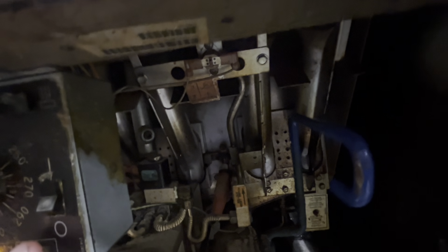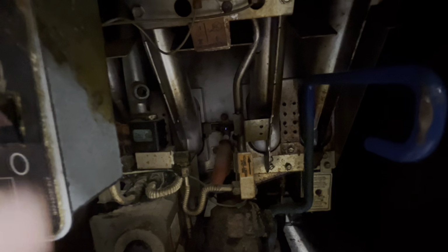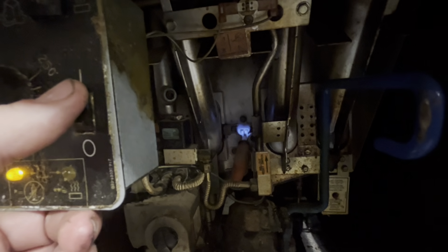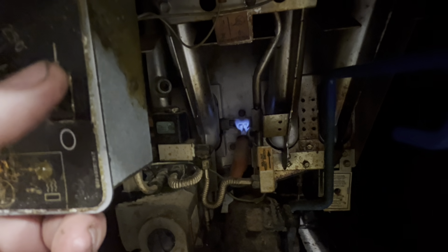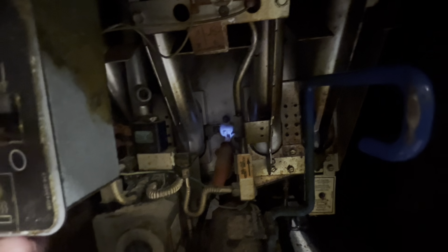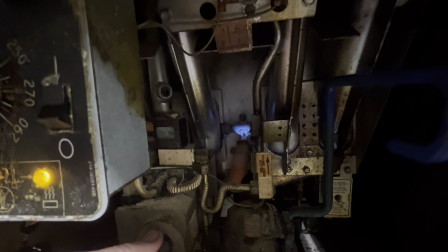Now, do you have no gas pressure here because we have a gas pressure problem with the valve? Or, so what I'm actually going to do is close that valve for a minute, reopen it. I'm going to give it a rush of pressure, try and flush the system a little bit. Right, so we could have a gas valve problem that's not letting enough gas through.